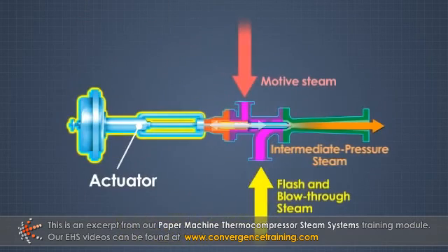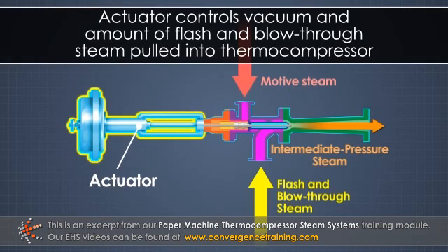The actuator moves the spindle toward or away from the nozzle opening to control the flow of motive steam through the thermocompressor nozzle. Therefore, it controls the creation of the vacuum and the amount of flash and blow-through steam that is pulled into the thermocompressor.